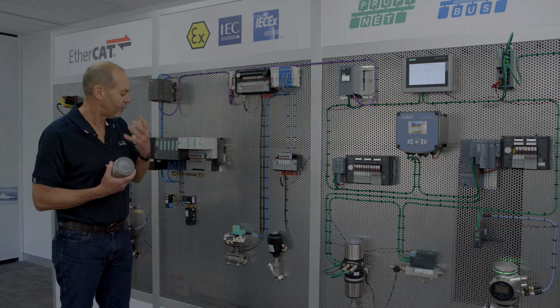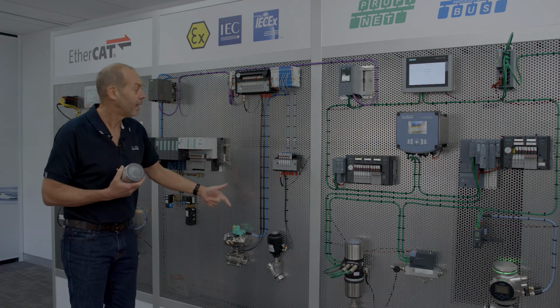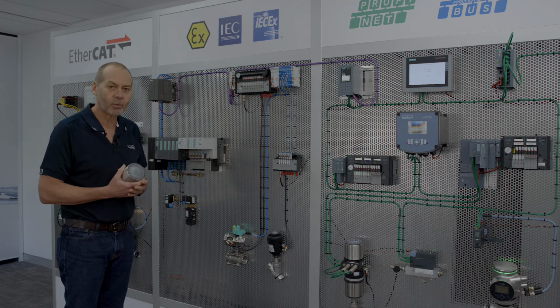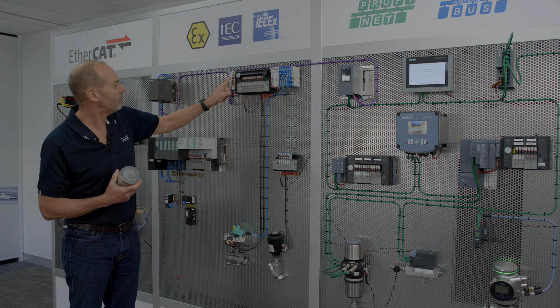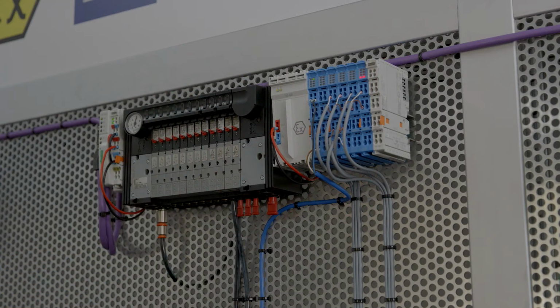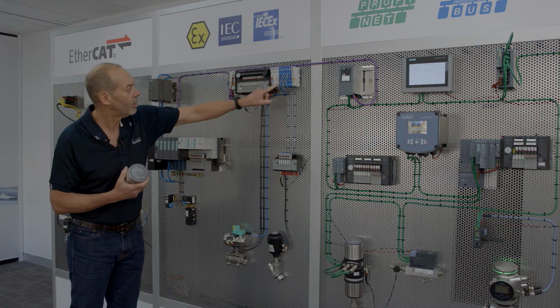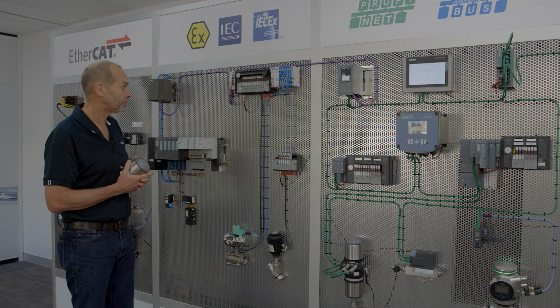But if we wanted to have feedbacks, of course, we're going to use a NAMUR feedback, and that's going to need to come back through a barrier. But that doesn't need to be hardwired either. On this same Profibus network, we run through the system and link into IEC-Ex approved barriers. In other words, we can run this feedback all the way back here, and we can see the valve position operating here.